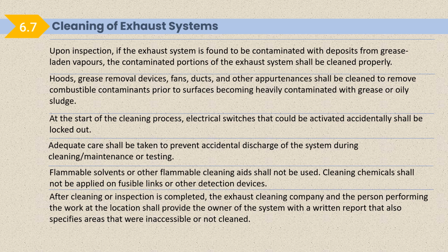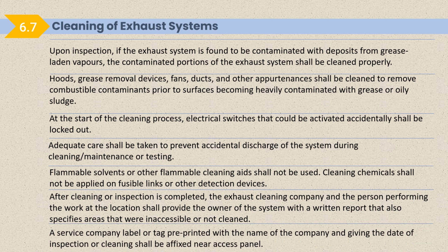After cleaning or inspection is completed, the exhaust cleaning company and person performing the work at the location shall provide the owner of the system with a written report that also specifies areas that were inaccessible or not clean. So these specific details need to be mentioned in the written report that is submitted by the cleaning agency. A service company label or tag pre-printed with the name of the company and giving the date of inspection or cleaning shall be affixed near the access panel.